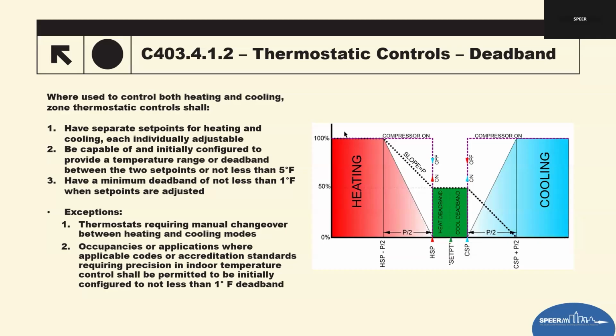One, we've got a manual changeover system. If the building uses thermostats that require a manual switch between heating and cooling modes, the deadband requirement does not apply. These systems cannot run both modes at the same time. Number 2, specific occupancy. For occupancies that require very precise temperature controls, such as labs, hospitals, galleries, clean rooms, or spaces governed by an accreditation standard, the thermostat can be set with a deadband as small as 1 degree at installation. These spaces are allowed tighter control because operation basically outweighs the energy savings of a wider deadband.